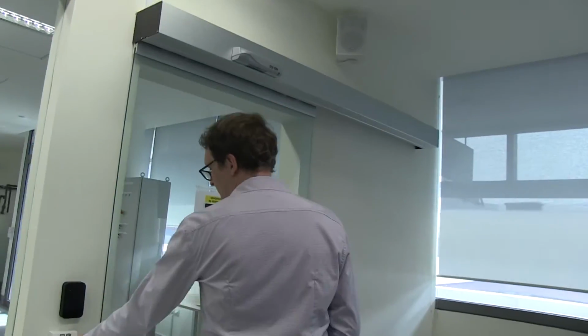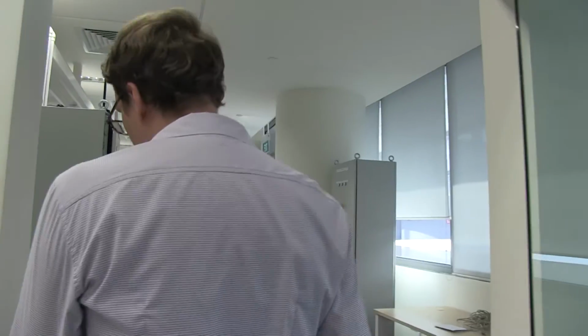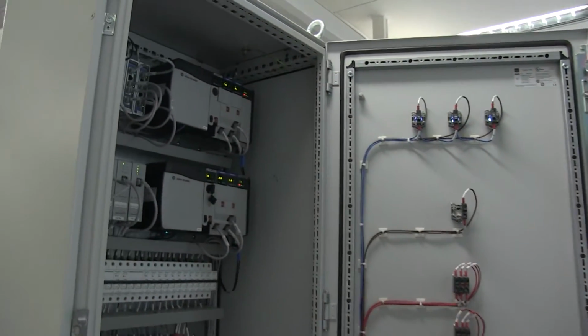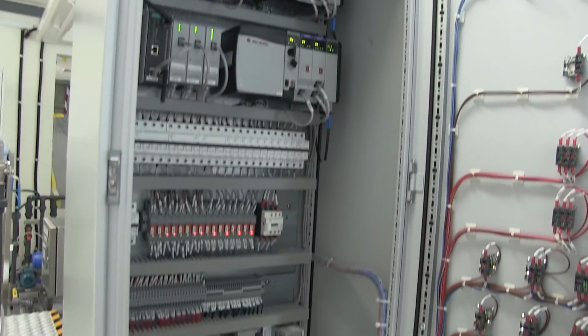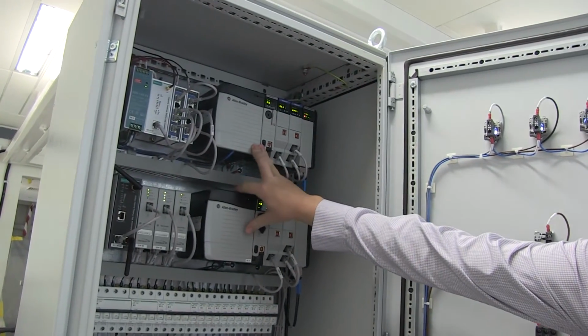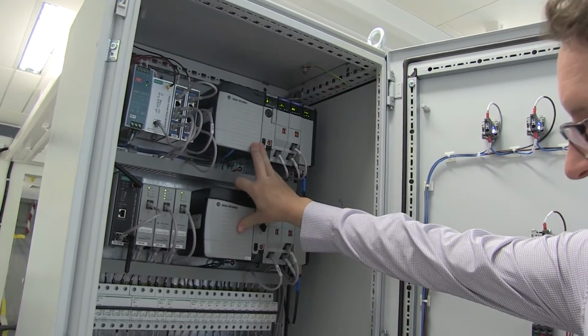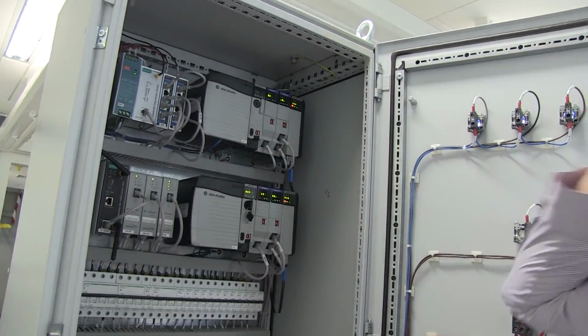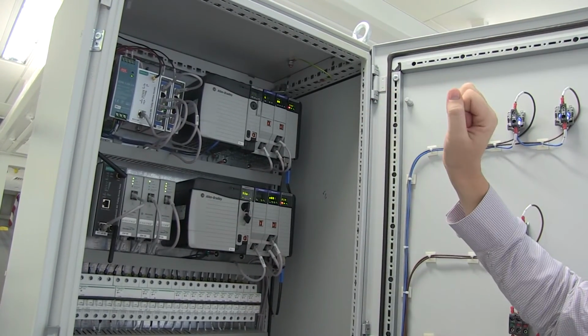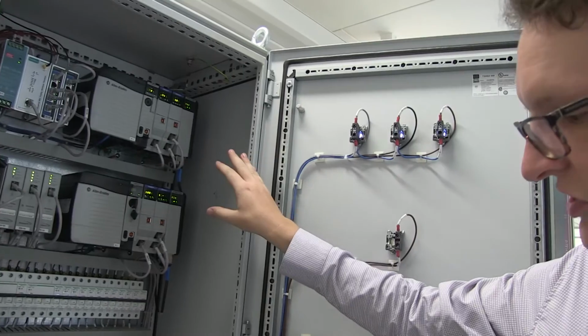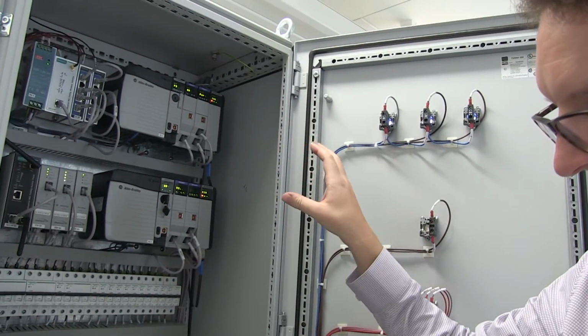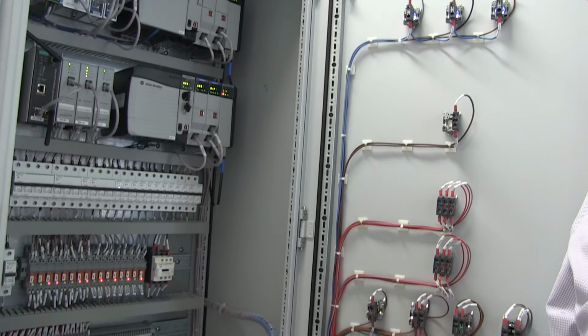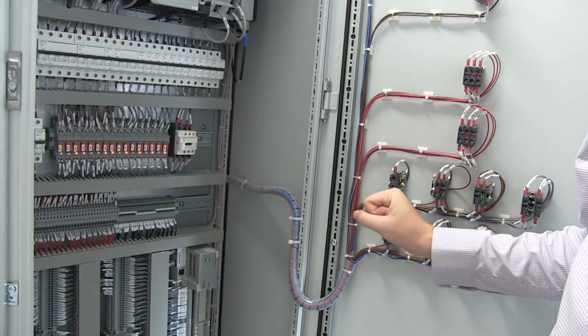So this was the level 1 network. Now we'll have a look at the level 0 network. Each process stage has its own cabinet which houses the main PLC and the backup PLC. The PLCs are of course connected to the level 1 network through a wired Ethernet, and in addition there's a second network, the level 0 network, in this cabinet. It's a ring topology, an Ethernet ring, which connects the PLCs with each other in redundant fashion, and in addition it connects them with the remote I/O unit and other components which are also able to talk Ethernet IP.